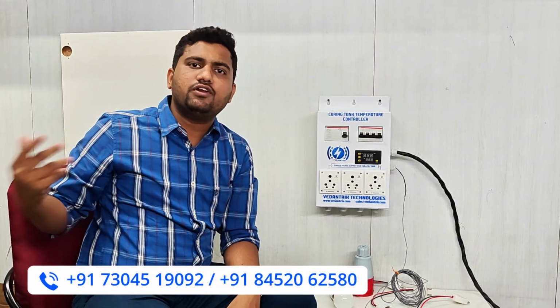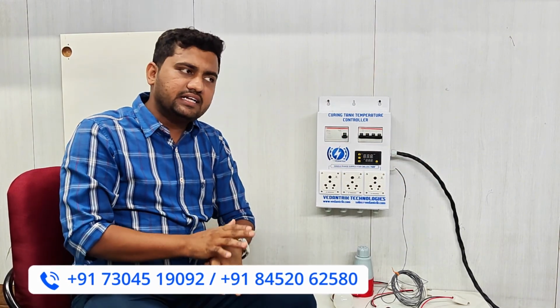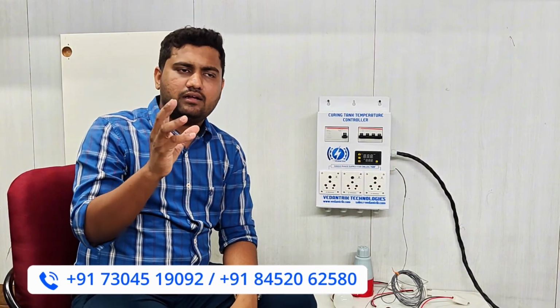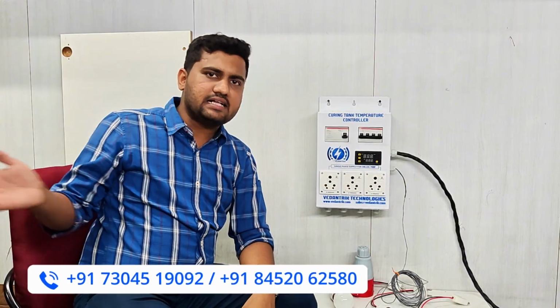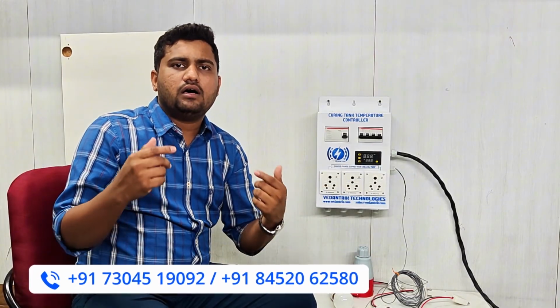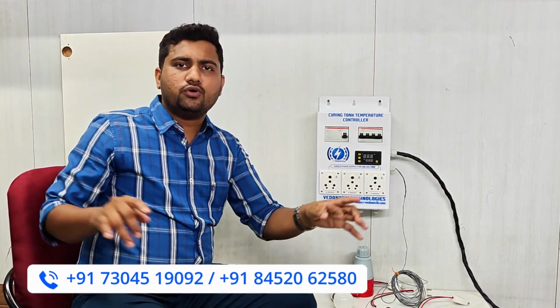So whenever one tank achieves 27 plus minus 2, the other 3 will also achieve 27 plus minus 2. If any of the tanks goes above 29 degrees Celsius, the heater can be cut off. You can just assume that if one tank is going above 29, the others will also, since all the heaters are of the same capacity, all the tanks have the same water volume, and all are in the same city, so all tanks have the same lowest temperature and will reach 29 degrees Celsius simultaneously. That's how, with a single controller, you can control your 4 tanks by putting this temperature sensor in any of the tanks.